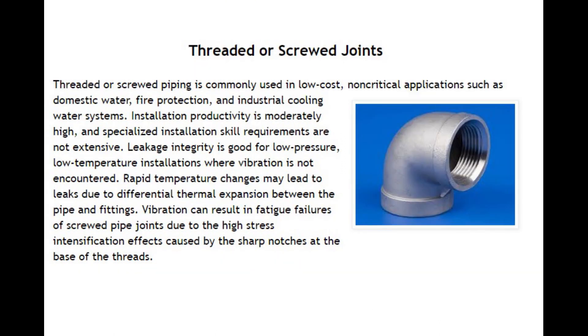Number 4: Threaded or Screwed Joints. Threaded or screwed piping is commonly used in low cost, non-critical applications such as domestic water, fire protection, and industrial cooling water systems. Installation productivity is moderately high, and specialized installation skill requirements are not extensive. Leakage integrity is good for low pressure, low temperature installations where vibration is not encountered.